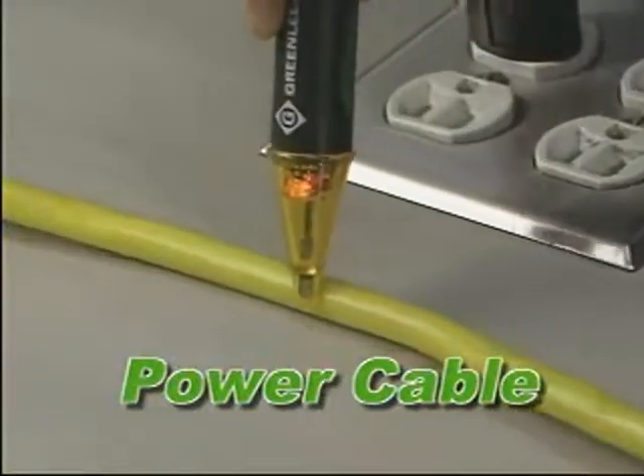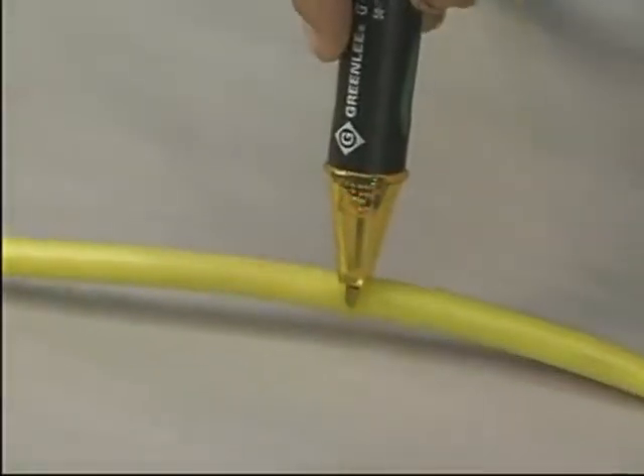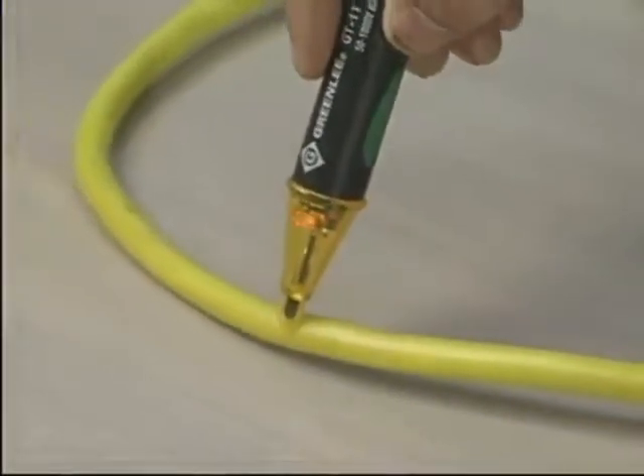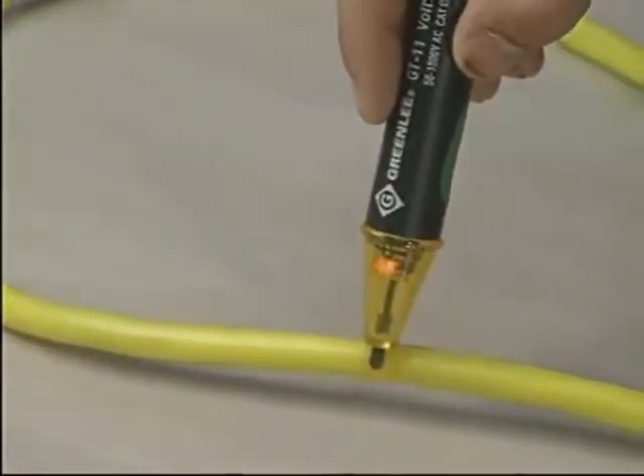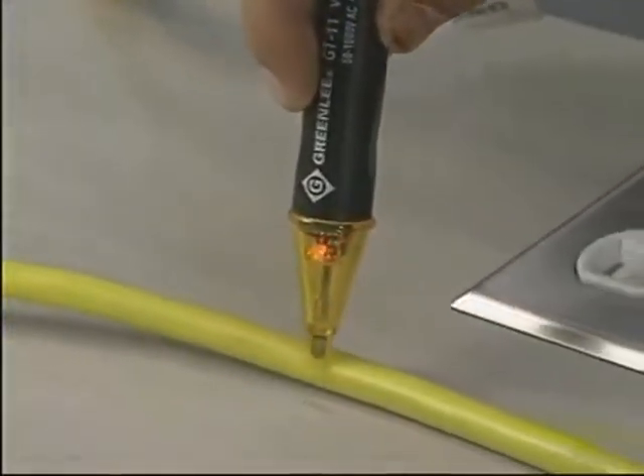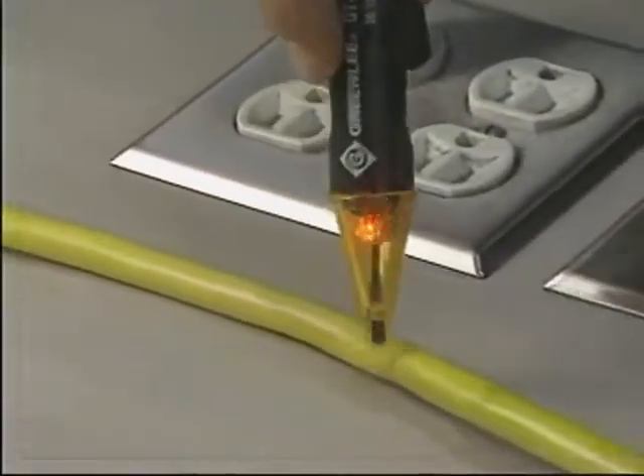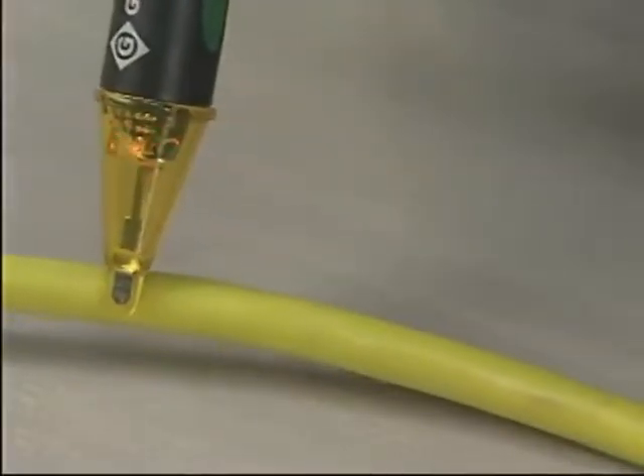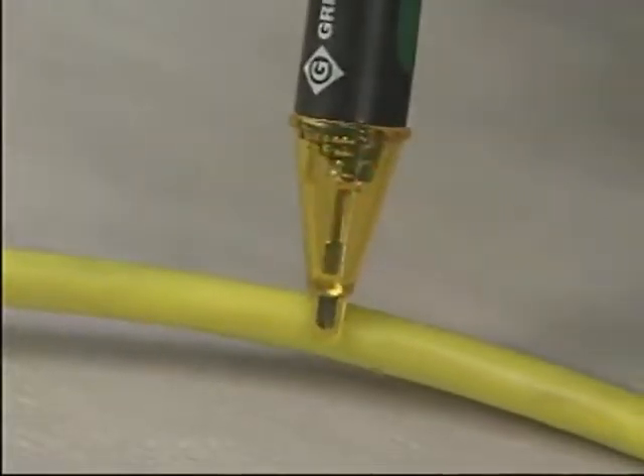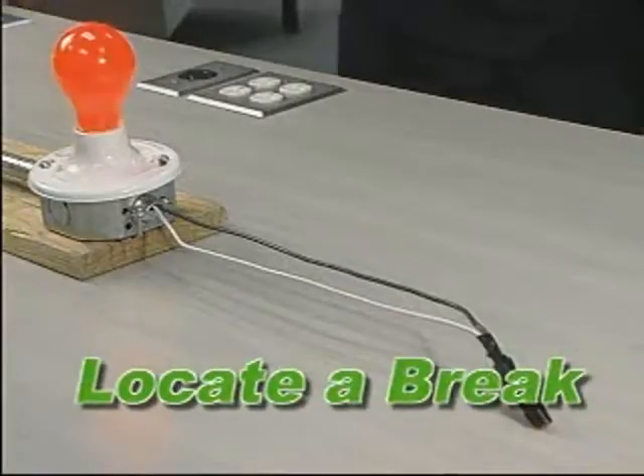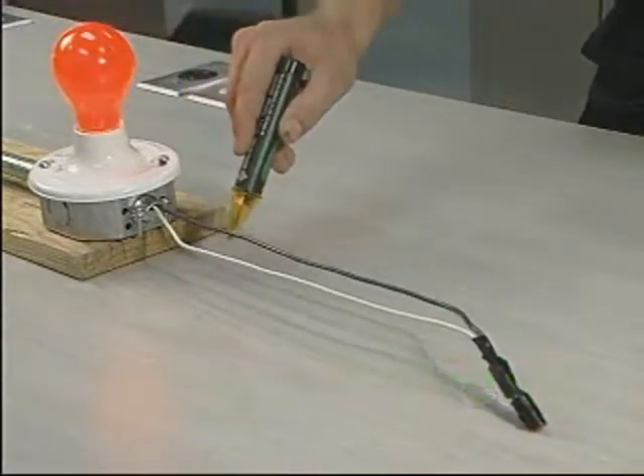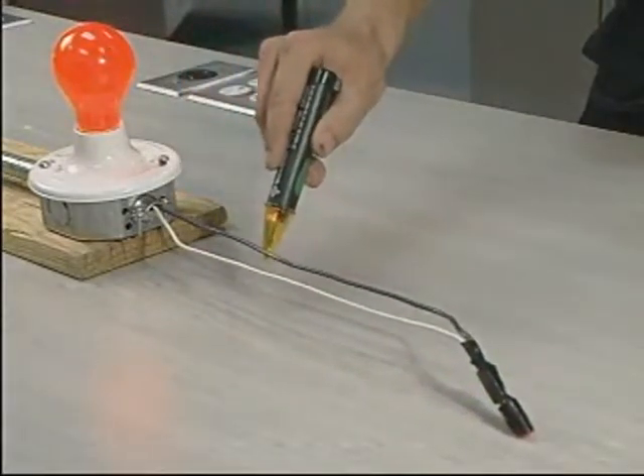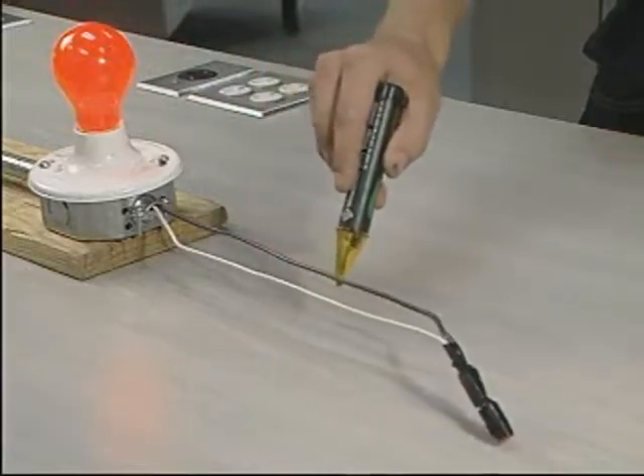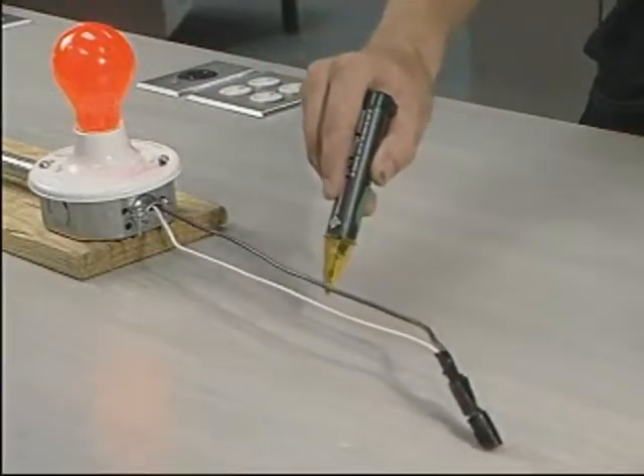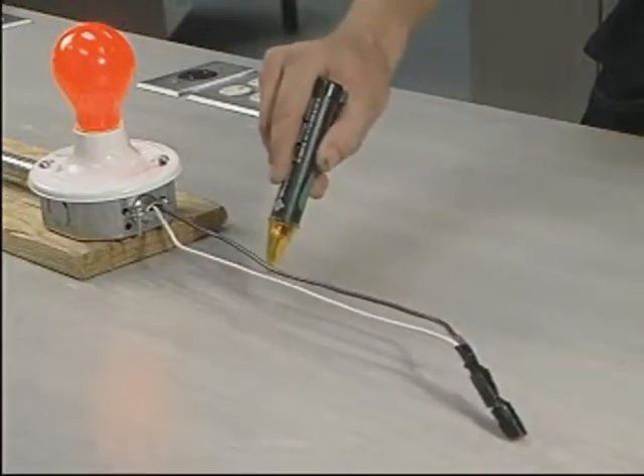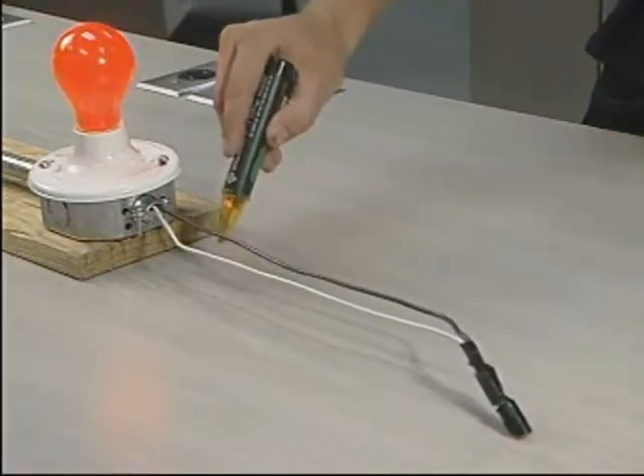Slide the flat part of the GT11 probe tip along the cord. You will get an intermittent audible and visual alarm. Because the conductors may be twisted, if you only check one spot, you may place the probe tip on the neutral or ground wire. Slowly sliding the unit along the cord assures that you'll pass the probe tip over the hot wire. To find a break in a hot conductor, run the probe tip along the conductor until the audible and visual alarm stops. Similarly, to find a break in a neutral conductor, connect a load across the hot and neutral and trace the conductor until the audible and visual alarm stops.